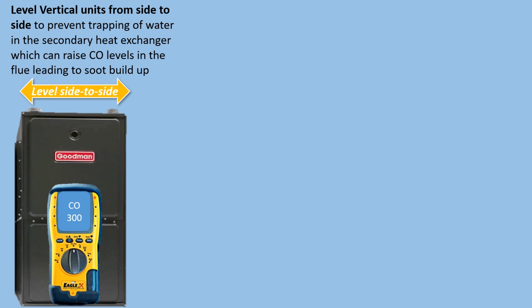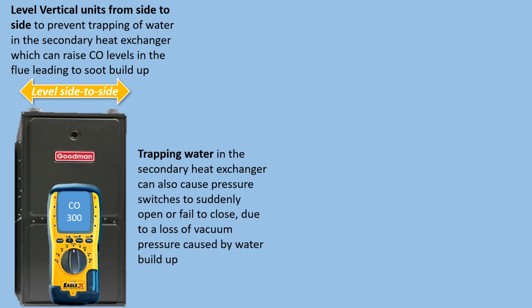Level vertical units from side to side to prevent trapping of water in the secondary heat exchanger, which can raise CO levels in the flue leading to soot buildup. Trapping water in the secondary heat exchanger can also cause pressure switches to suddenly open or fail to close due to a loss of vacuum pressure caused by water buildup.